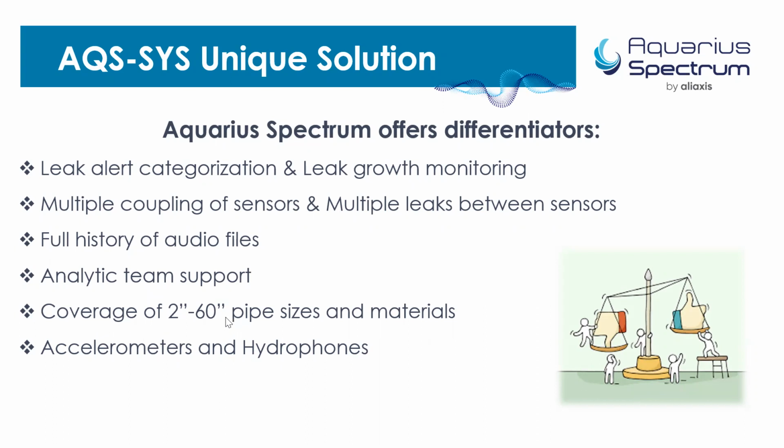And we cover all pipe sizes with our technology, from diameter 2 inch to 60 inch. That would be about 5 cm to 1.5 meter diameter in terms of pipe diameter, and all pipe materials, thanks to the use of accelerometer and hydrophones.